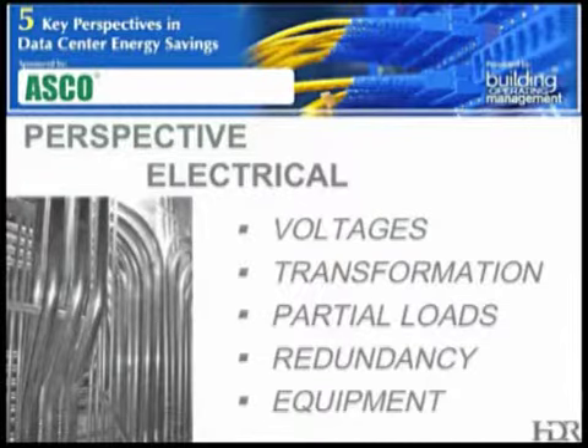Also, one item we deal with a lot is the redundancy or reliability of the system and how that affects partial loads. Most UPSs and PDUs operate around 40% of the rating. If we have a 2N system or redundant system, it could be down to about 35%. So understanding the system efficiency under part loads and what the anticipated loads are expected to be is important. You need to study the equipment efficiency curves at these part load conditions. Maybe employ a growth plan with multi-module systems instead of putting all your capacity in at once. And select your redundancy carefully and take those load ratios into effect. Sometimes it's better to base your redundancy on a reliability analysis rather than just saying I want a 2N or an N+1 system, and then optimize that to the application involved.